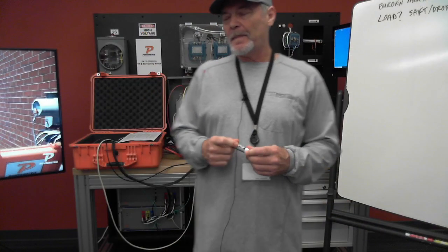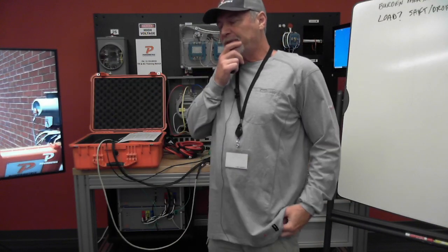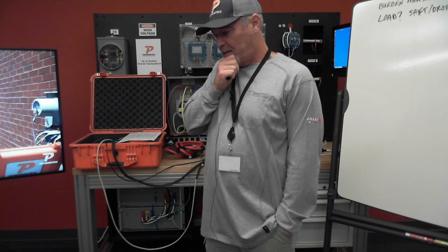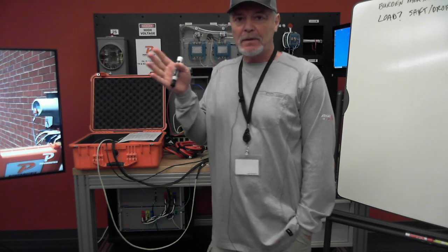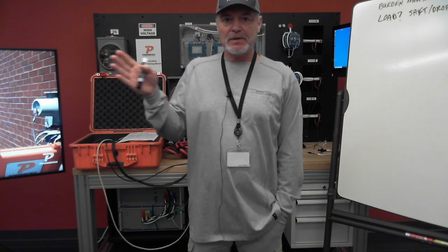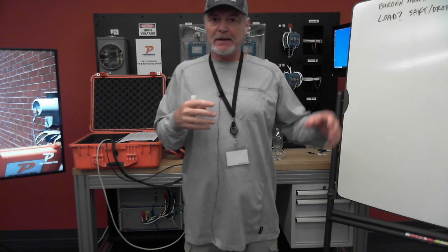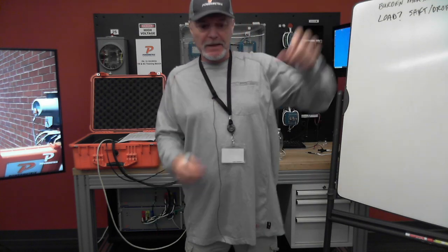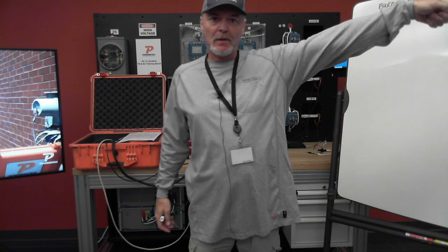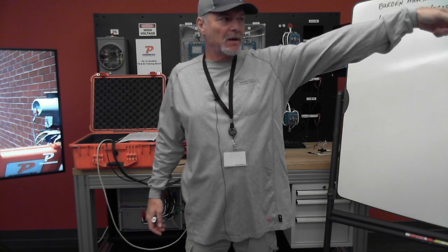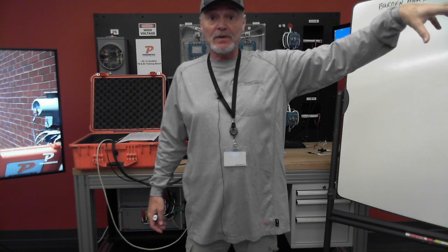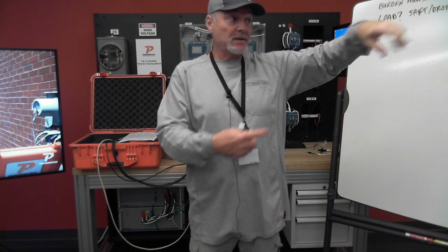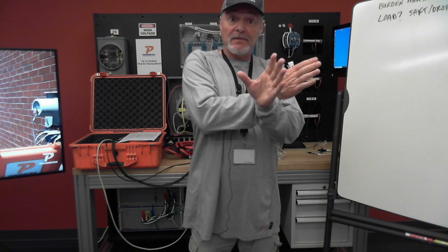Okay, so a few things here. So we're at this point in it, and you have to check your stuff first to make sure you don't have something that's wrong, right? So we checked all the way starting from where the flexes went around the conductors in the pad mount. So we checked to make sure it wasn't that initial connection, which was the flexes. It wasn't the flexes. We swapped them. It didn't follow the flexes.